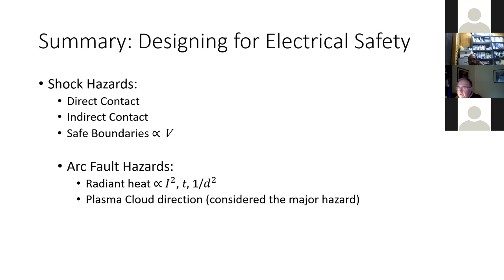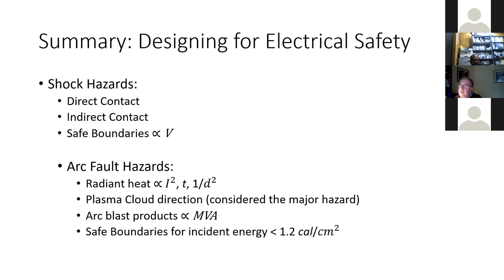One really important point to note on direction is I mentioned that the plasma cloud is much lighter than air by virtue of all the atoms being stripped of their electrons. That means there's a much greater risk to people working on top of a switchboard or above a switchboard. And then the other arc fault hazard is the blast. And the arc blast is considered more in relation to power rather than energy. And the safe barriers for incident energy are just any incident energy less than 1.2 cals per square centimeter.